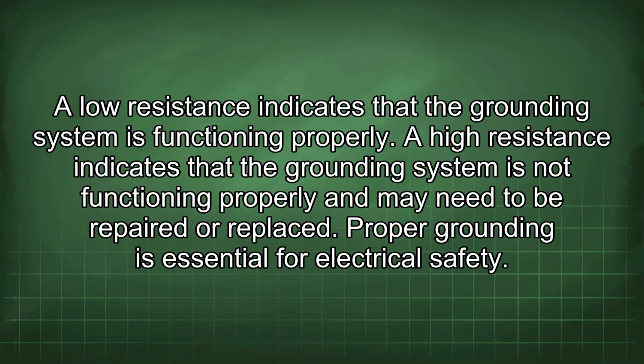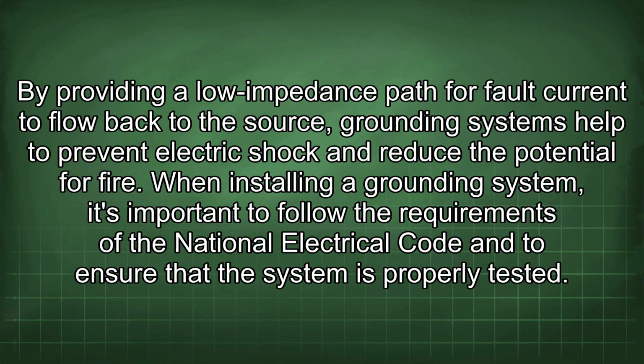Proper grounding is essential for electrical safety. By providing a low impedance path for fault current to flow back to the source, grounding systems help to prevent electric shock and reduce the potential for fire. When installing a grounding system, it's important to follow the requirements of the National Electrical Code and to ensure that the system is properly tested.